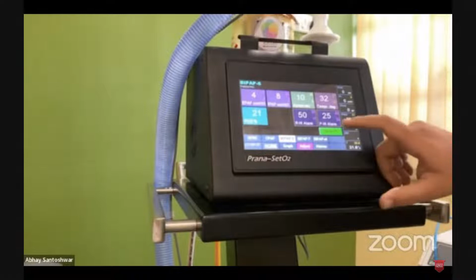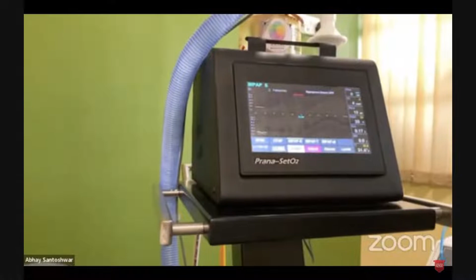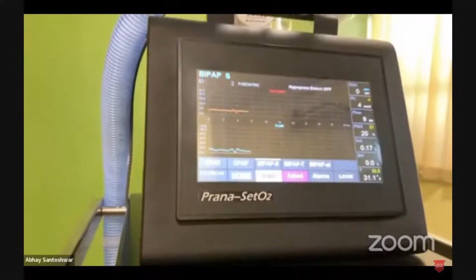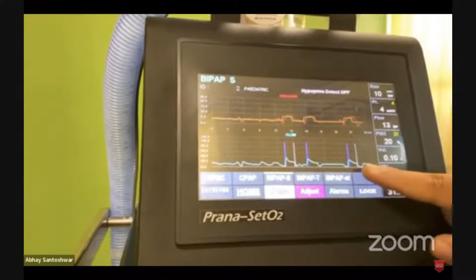In BiPAP S, this is a spontaneous mode. So please start. And since this is spontaneous, initially the machine is going to set some PEEP level on which the patient is allowed to breathe in. When the patient breathes in and crosses the trigger threshold, he is given the IPAP pressure. And the moment he makes some expiratory efforts, you are able to sense the expiratory trigger as well and cycle him off. So in a typical BiPAP S mode, you are able to see very emphatically the triggers, the inspiratory as well as the expiratory triggers.